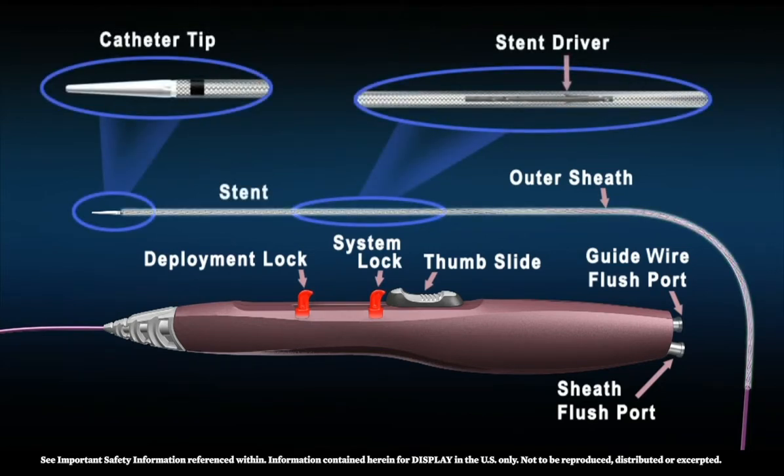Note that the Supera implant is constrained at approximately three times its nominal length within the delivery catheter. Proper deployment is critical to restoring the Supera implant to its nominal state, maximizing its radial strength and flexibility.